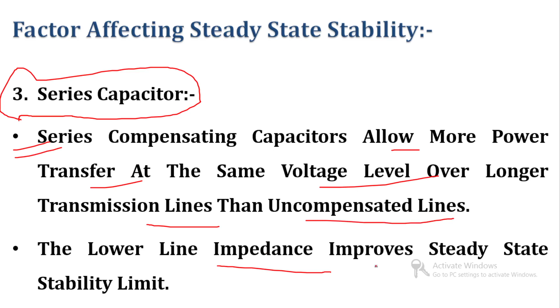So if we compensate the transmission line with a series capacitor, as you can see in this diagram, this is the normal reactance of the transmission line, and if we put a series capacitor bank in series with the transmission line, then the net reactance of the transmission line gets changed. You can see over here that for a normal line the reactance is Xt. If the line is compensated by means of a series capacitor, then the reactance will change from Xt to Xt minus Xc. So we can say that reactance will reduce. Due to that, power transfer capability will increase, and due to that, the steady state stability limit will also increase.